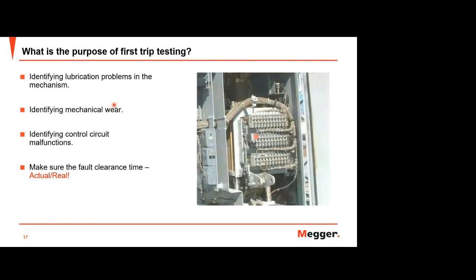And also identifying control circuit malfunction, because as you know, we also try to see the response of the auxiliary contact to stop the coil current, to stop the voltage injected to the coil. So if there is an issue on the auxiliary contact, we can also see it from this first trip. So we can identify it with the first trip testing.